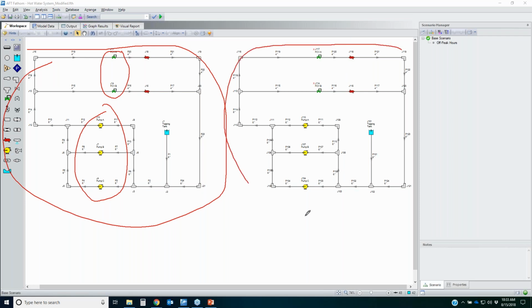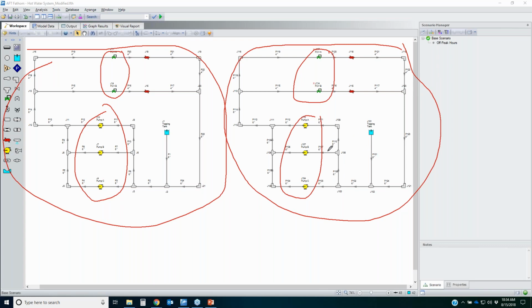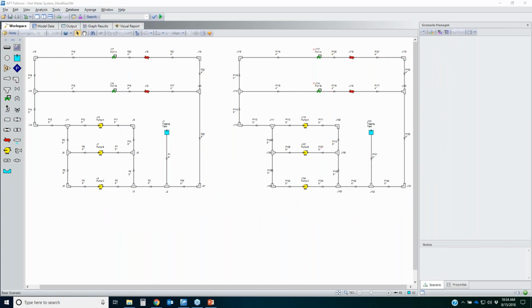The system on the right-hand side is the same system, but what I've done was I failed these control valves open and they have no loss. It's like they're not even there. The reason why is because I'm going to operate the pumps in this case on variable speed drives. So rather than controlling to a set point with my control valves, the pumps are going to control to a set point. And we're going to evaluate exactly what the cost savings are. Now, I have 2 scenarios. I've got a base scenario and then I have an off-peak scenario. My base scenario is normal operating conditions of a total system flow rate of 3,000 gallons per minute.